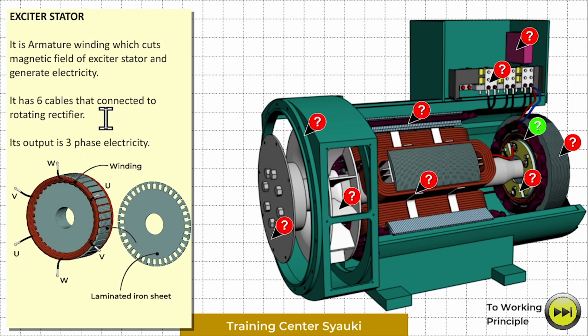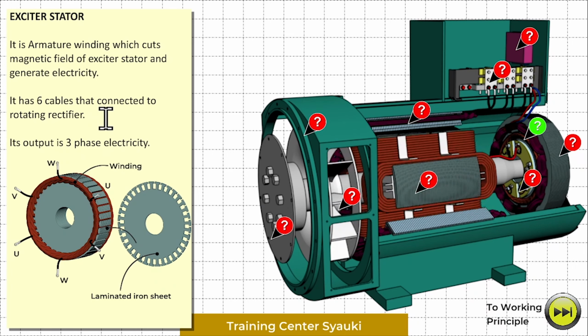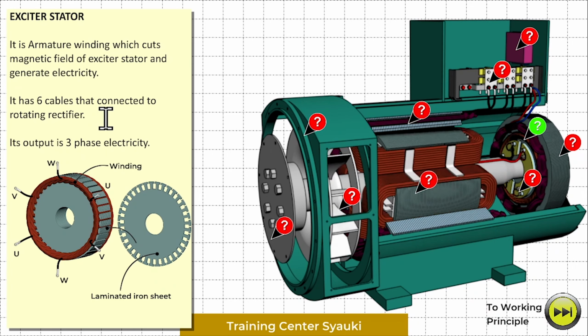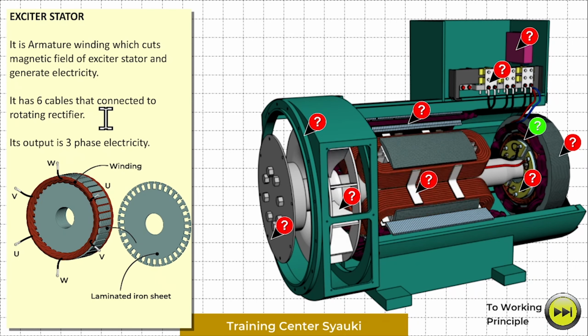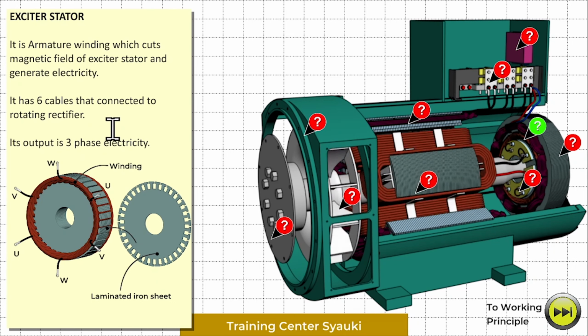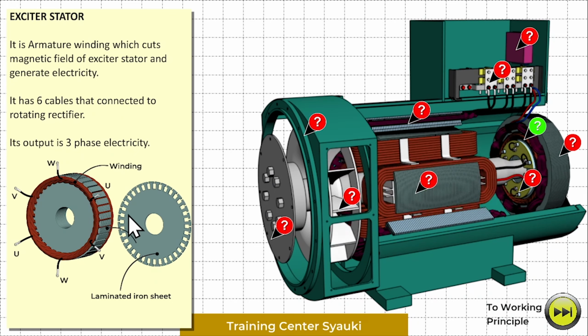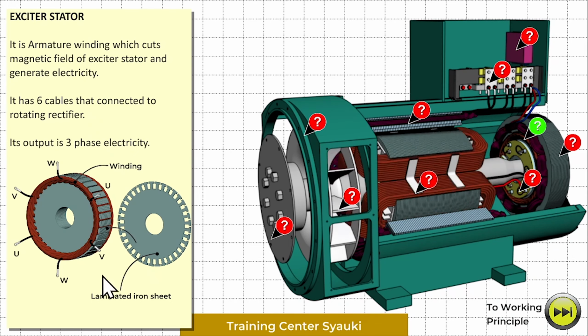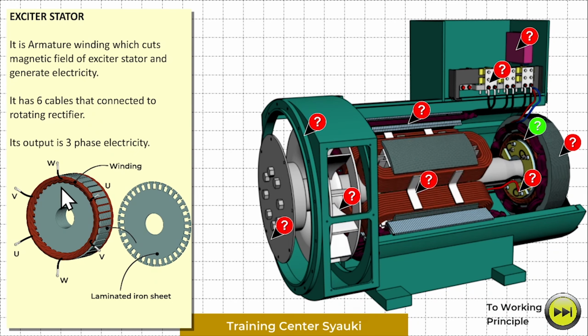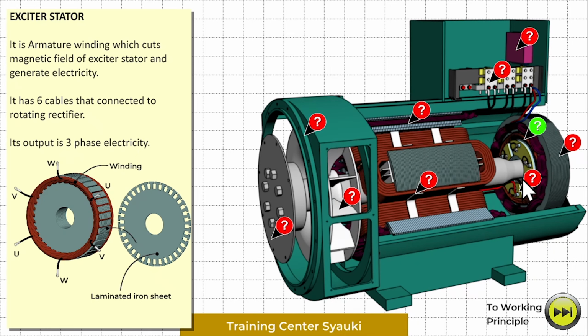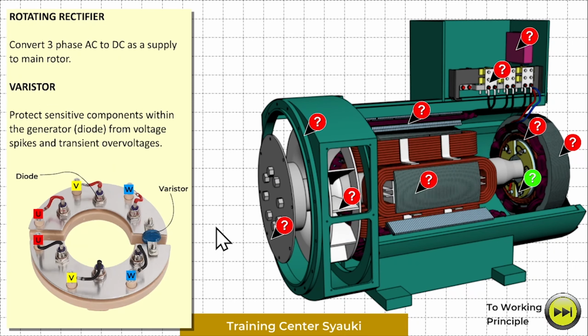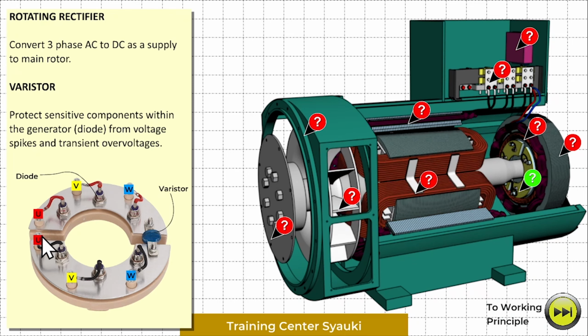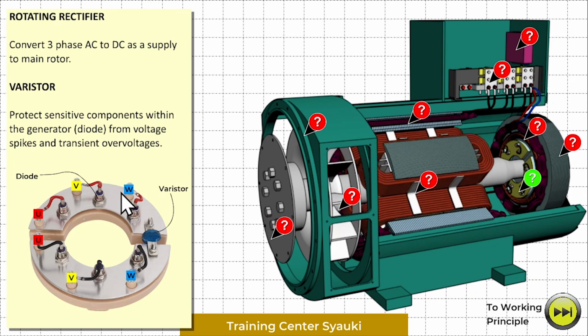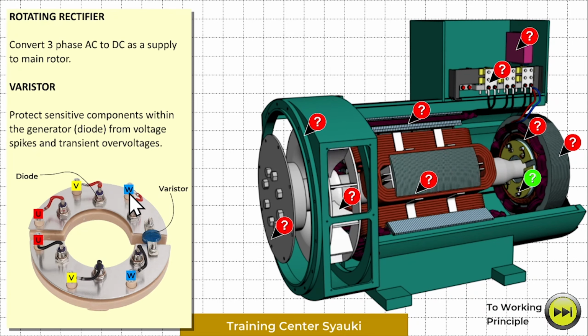It has 6 cables that connect to rotating rectifier, but its output is 3-phase electricity. Why 6? It's only 3-phase. Why 6 cable? Because 6 cable will connect to rotating rectifier here in U, V, and W.